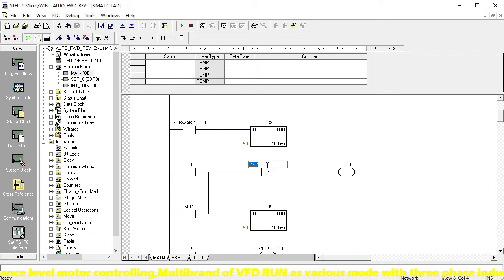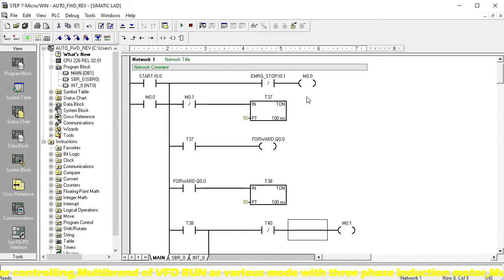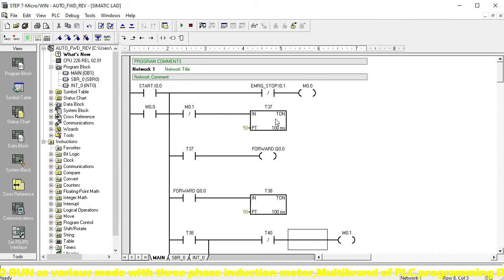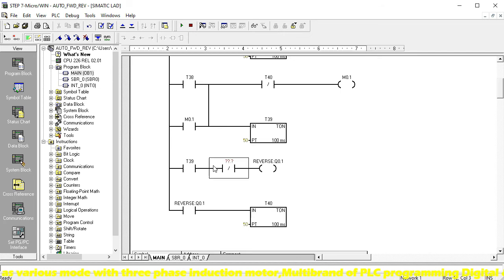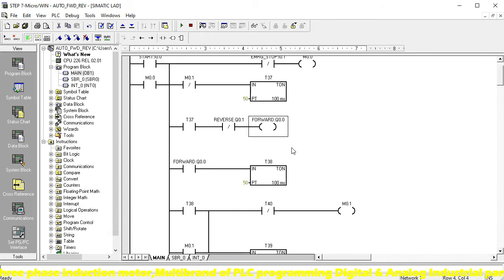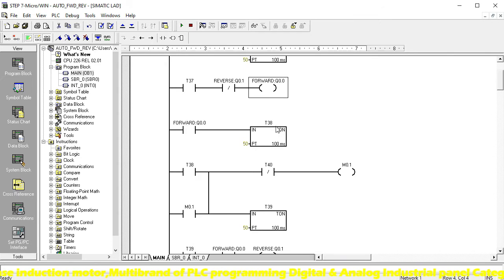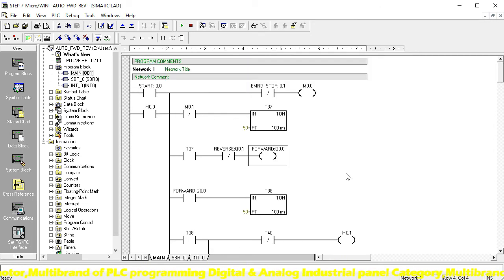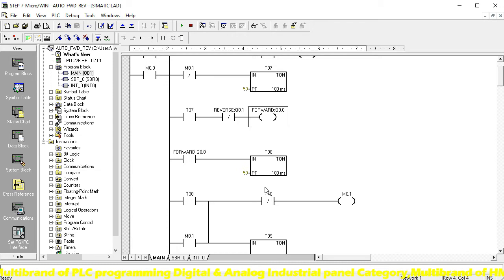When T40 times out, our Reverse is stopped. This is the programming relay, and it's a break contact for memory relay M0.1 — when this side stops, that means Forward stops. Then when we stop this side, it will continue because of the interlocking system. This is very important — Q0.0 and Q0.1 form the interlocking system. This is the automatic Forward/Reverse: first a five-second delay, then Forward runs.